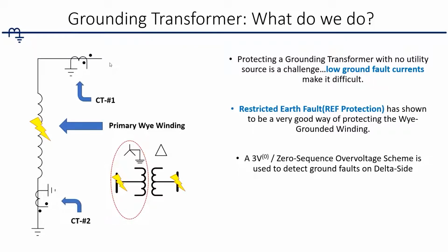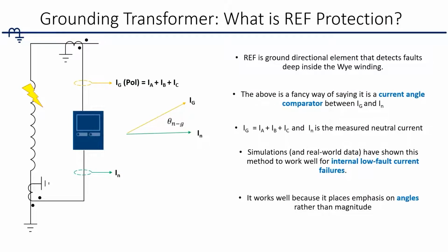That protects specifically the Y grounded winding. On the delta side, there's a classical ungrounded circuit protection, which is your 3V0, zero sequence overvoltage. That's what a lot of folks are using for that side of the transformer to protect for ground faults. They'll install PTs on the secondary and then monitor that using a protective device. So we'll talk a little bit about getting into the protection aspect. We'll talk a little bit about what REF protection is. It's a pretty misunderstood thing, even among protection engineers within the community.